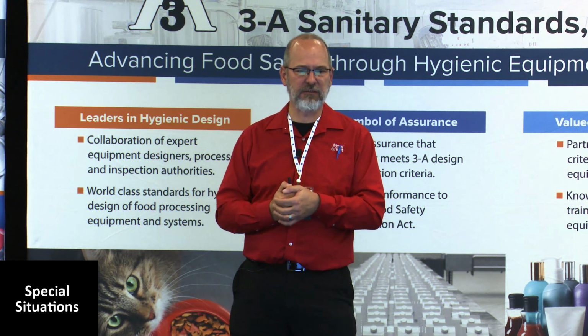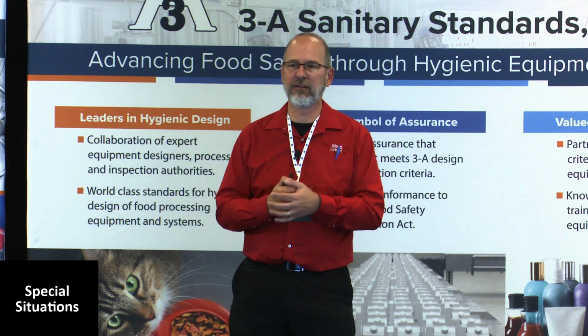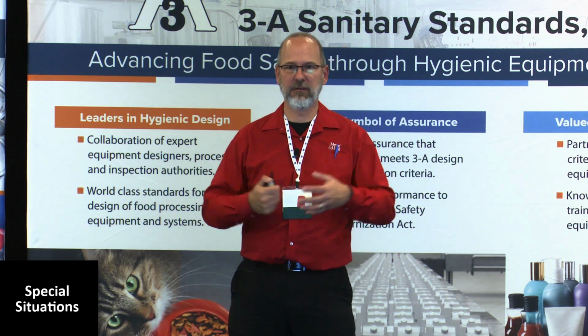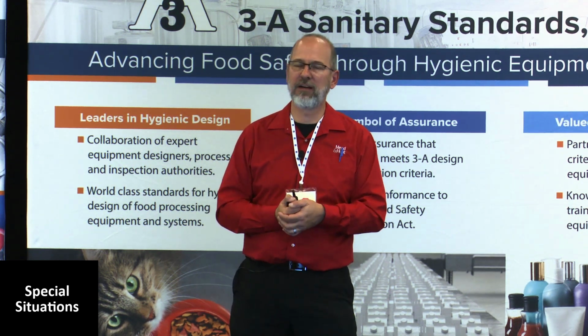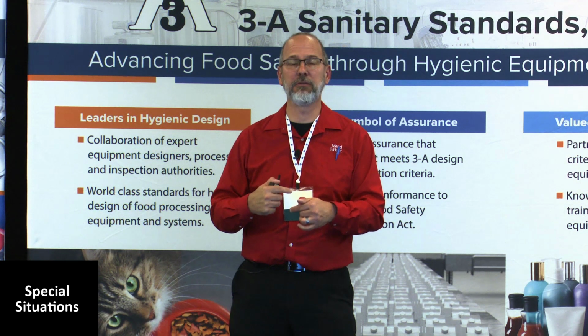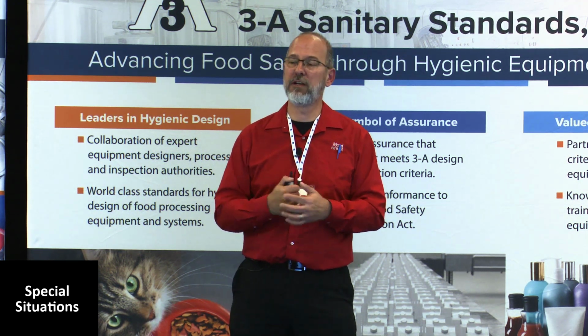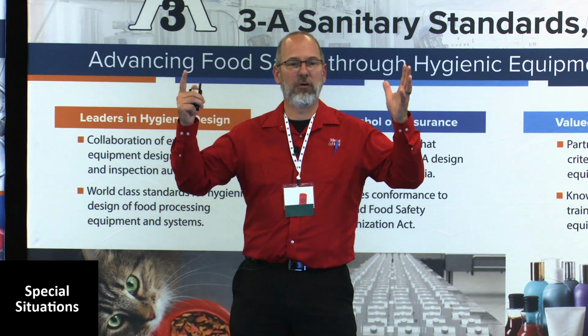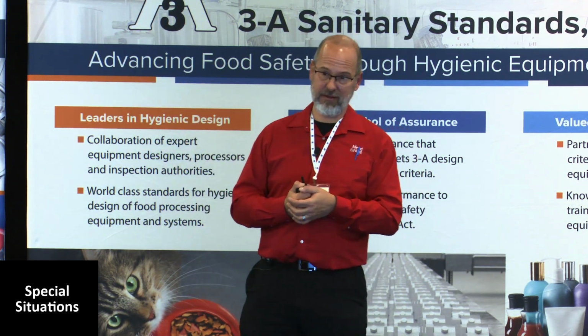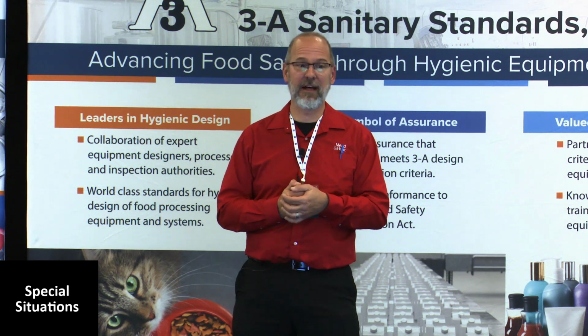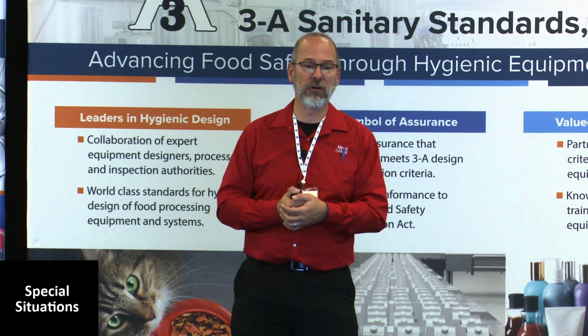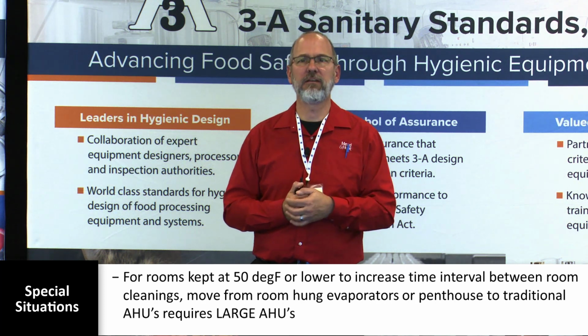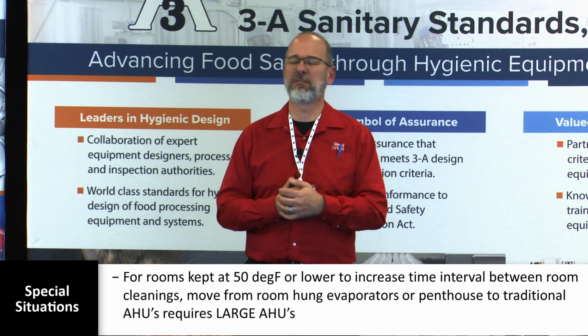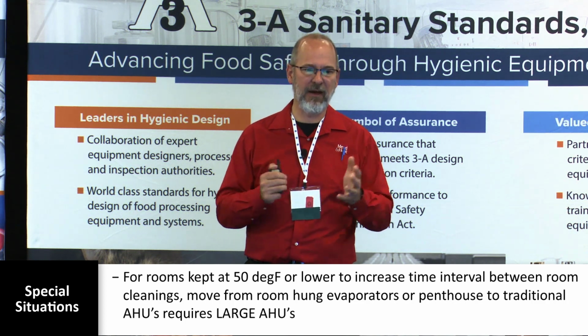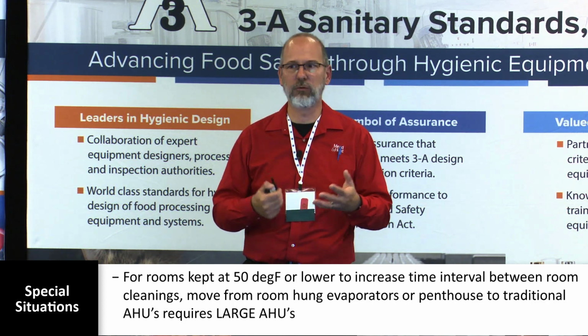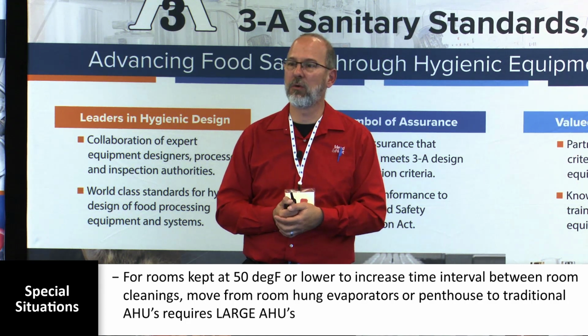And that works, but just as a word of warning, when you do that, the air handlers get really, really big. If you have a 10, 20,000 square foot processor and you're trying to keep below 50 degrees so you don't have to shut it down to clean up quite as often, you may go from 8 small evaporators hanging in the room to 4 air handlers on the roof that are $250,000 a piece and weigh 20, 30,000 pounds. So at the 50 degree mark, roughly, air handling units start to go up exponentially in size. So just something to keep in mind when you're thinking about either modifying a room or building a new room that's got that kind of low temperature requirement.